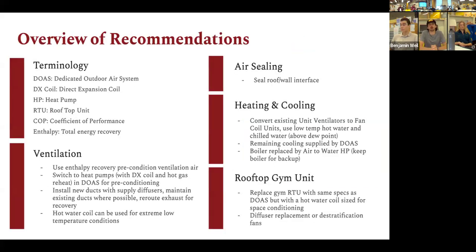So just a quick overview of the recommendations that we had planned. For ventilation, we want to use enthalpy recovery to precondition the ventilation air. We want to switch to heat pumps with a direct expansion coil in the dedicated outdoor air system to precondition that air. We want to install new ducts where possible, but use the existing ones that we have there and reroute the exhaust for recovery. And we want the hot water coil to be used for extreme low temperature conditions.